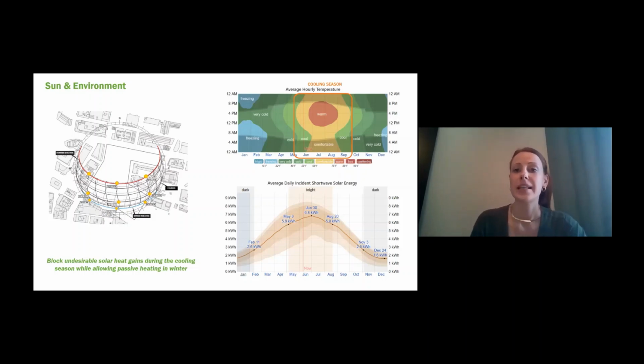Basically what we're seeing is, no big surprise, the project is in the Northeast. We have a pretty cold winter and some hot hours in summer. If we combine this hourly temperature with the incident solar radiation graphs, we see that our problematic or undesirable solar heat gain will likely happen from May to August, as the solar radiation is highest and we have high outdoor temperatures.